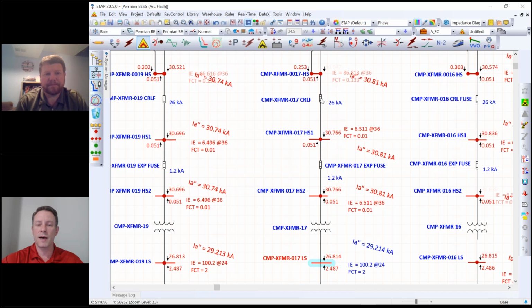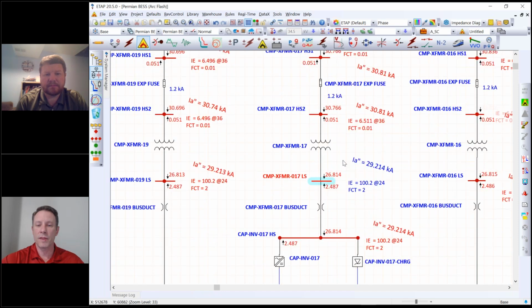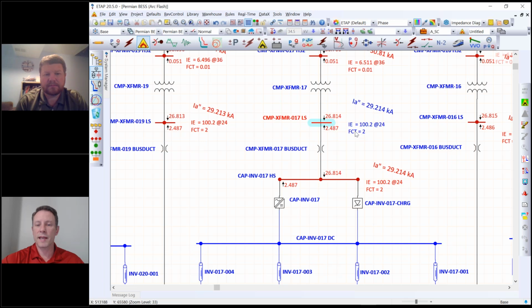I don't think these fuses are doing anything to lower this. That's why we get a 2 second fault clearing time for the low side. So those fuses could maybe be changed, and this model might have been updated since I got a copy of it, so it could be that we did do some mitigation there.